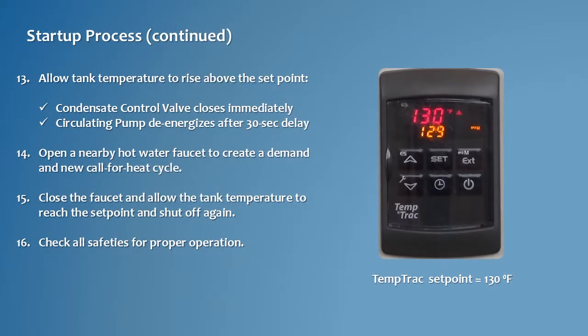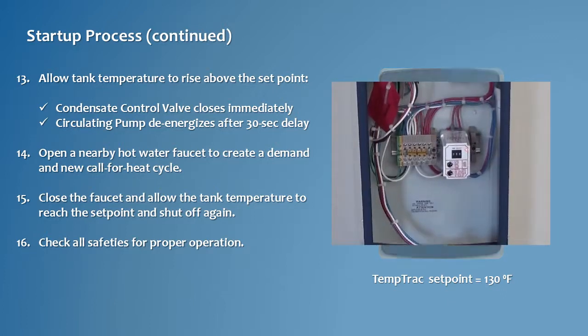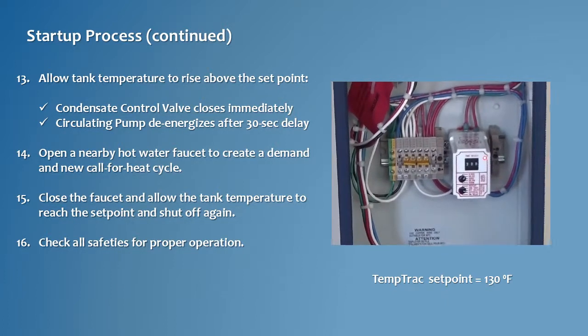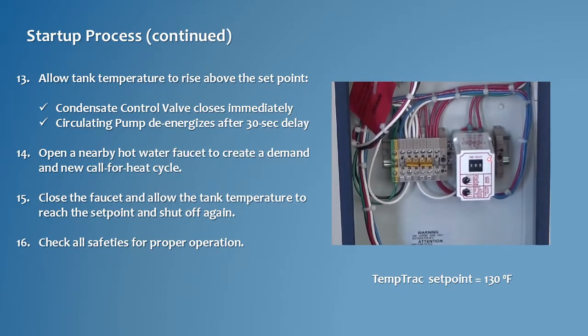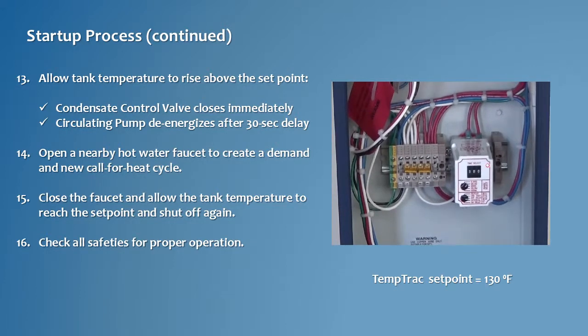Allow the water temperature in the tank to rise above the TempTrac control set point. The control circuit should open and immediately de-energize the condensate control valve, followed by the circulation pump after a preset delay of about 30 seconds. A fast blinking red LED is displayed during the time delay period. When the delay period ends, the red LED stops flashing and the circulation pump is de-energized.